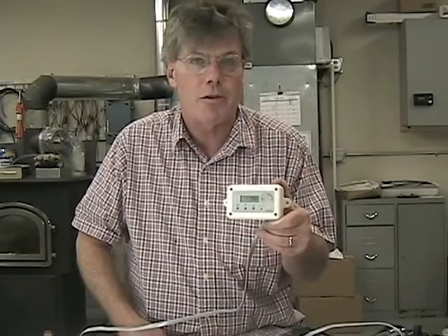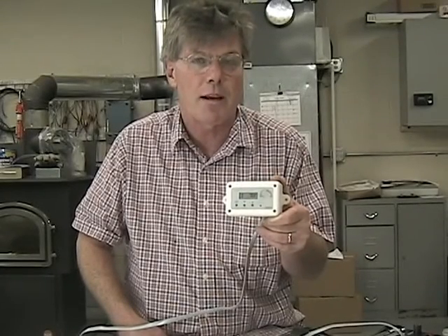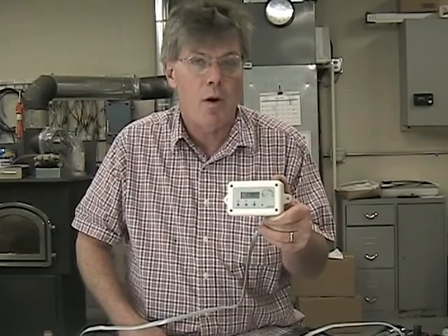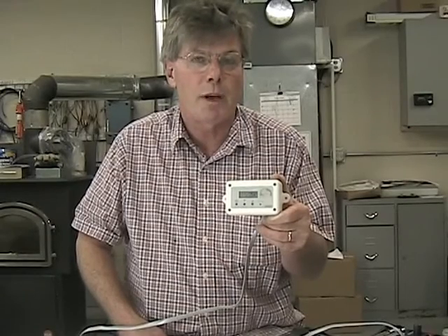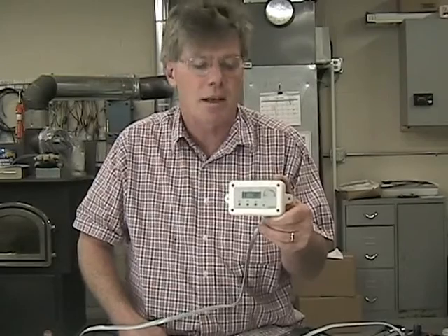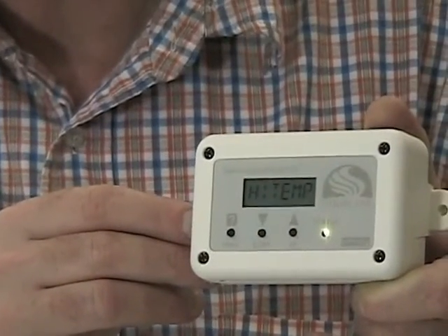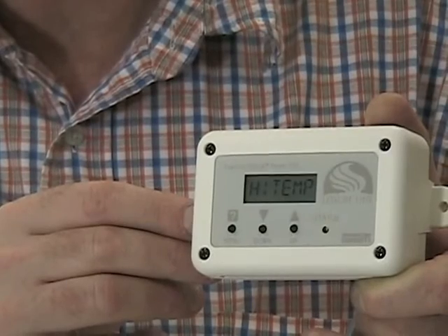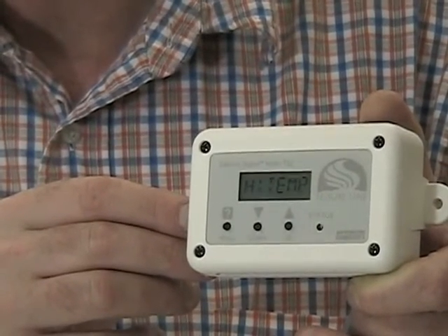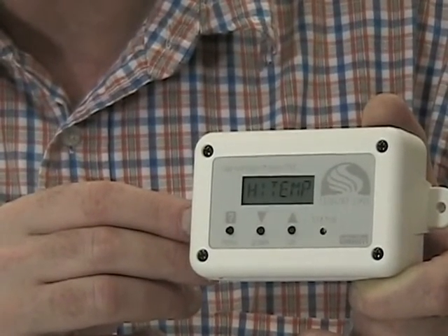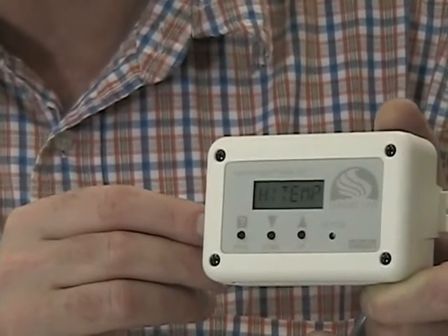One of the safety features of the Coal-Trol thermostat is a mode where if the room temperature sensed at the thermostat exceeds 98 degrees, your stove will stop feeding and it will shut down, and the fire will go out. Once the high temperature indicates on the display, to reset this and go back to normal operation, two things must occur.